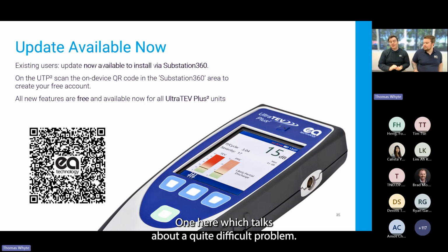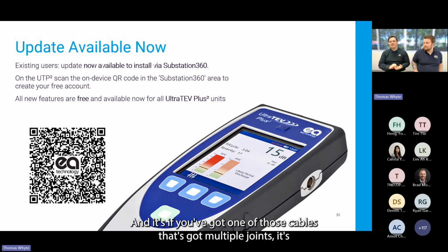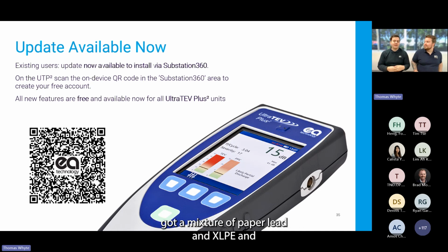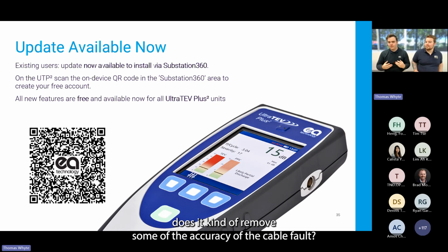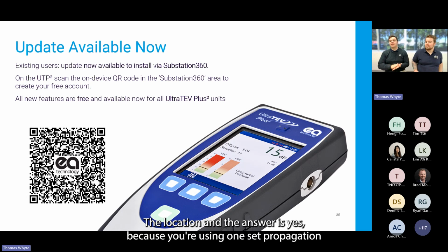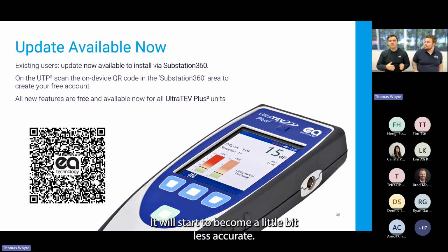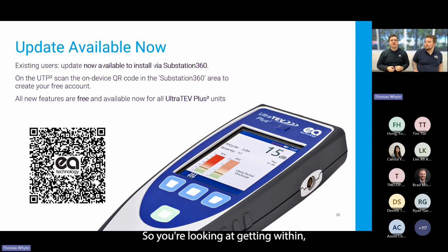One question talks about a quite difficult problem: if you've got a cable with multiple joints, with a mixture of paper lead and XLPE, does that remove some of the accuracy of the cable fault location? The answer is yes. Because you're using one set propagation speed, it will start to become a little less accurate the more joints you have and the different cable types. So you're looking at getting within a percentage, quite close.